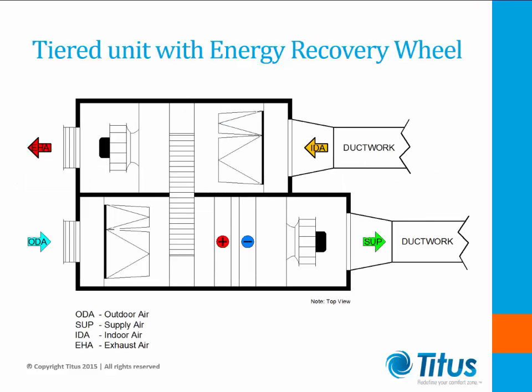Another configuration, and a more notable trend in the market, is the use of energy recovery wheels within AHUs. An ERV uses site-recovered energy from a building exhaust to precondition outdoor air for temperature and humidity. This dramatically reduces building energy cost. Preconditioning the air reduces the load on the heating and cooling system, reducing energy demand for treating outdoor air by up to 80%. A reduced workload complements energy cost savings and allows downsizing of HVAC equipment for an immediate return on investment.